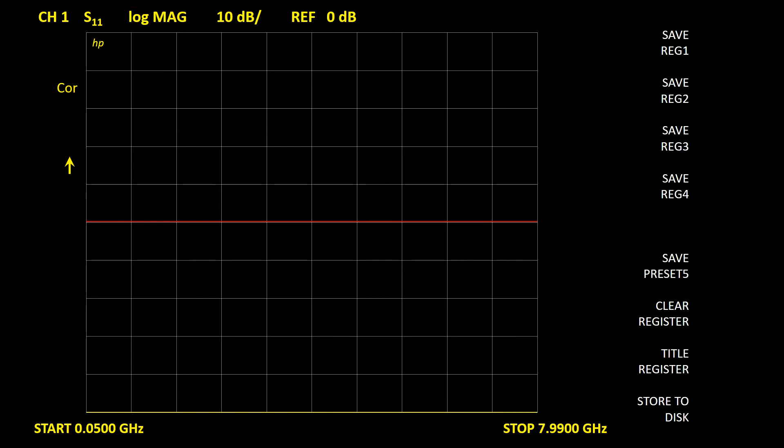After the calibration, the instrument displays the soft keys of the Save menu. We can save the calibration coefficients in one of the registries. We only need to choose one of them. If we choose register 5, the instrument state and calibration data will be automatically recalled during power on or after pressing the Preset key. Now we are ready to measure.